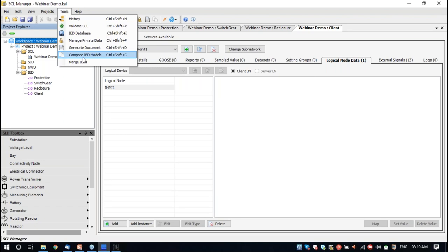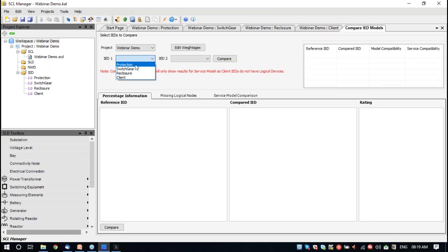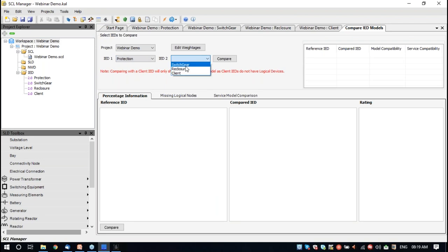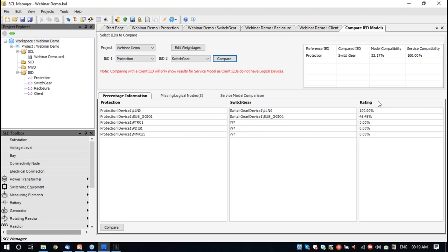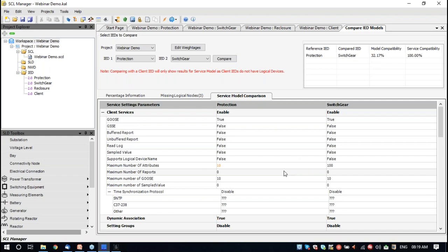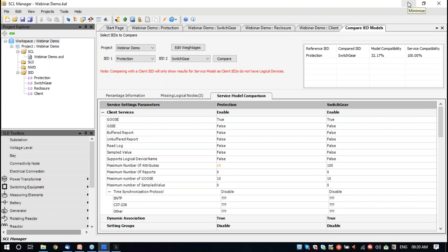Similarly, if you want to see only the signal exchanges involving the recloser, it will automatically do that. This feature will be handy to make an export with a subset of IEDs. There is also an option to change the target schema, since some IED tools may not accept all schemas. There is also a compare IED model feature where IEDs can be compared once imported to the tool. It will give the compatibility between these IEDs, so if you want to compare between two manufacturer IEDs from a service perspective or an IEC 61850 feature perspective, it is possible to do that here.